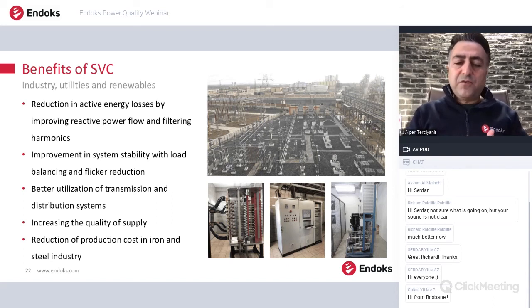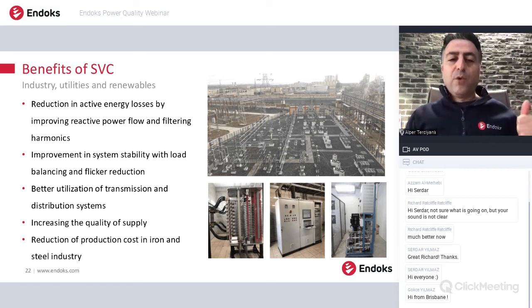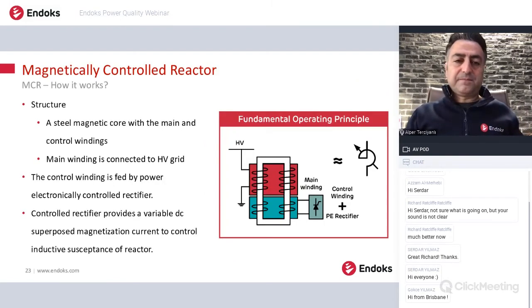This eliminating the reactive power means the better utilization of transmission and distribution systems, it's very important, and also increasing the quality of the supply because of eliminating the harmonics. So SVCs are very common in industry, and also in utilities, in grids, also SVCs are being used, especially for large systems. In order to have more stable power grid, we are using SVCs for reactive power support and also voltage support. And these are big systems, like starting from a couple of hundred MVARs.